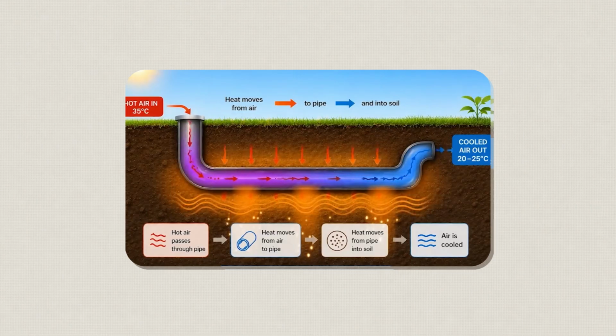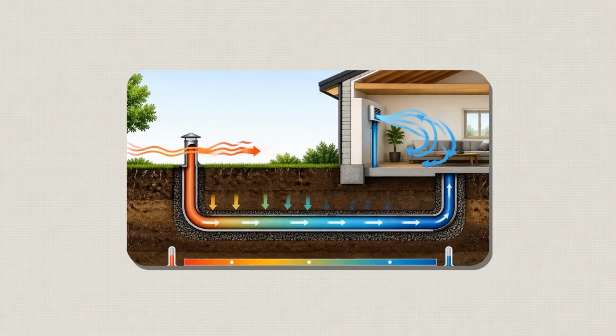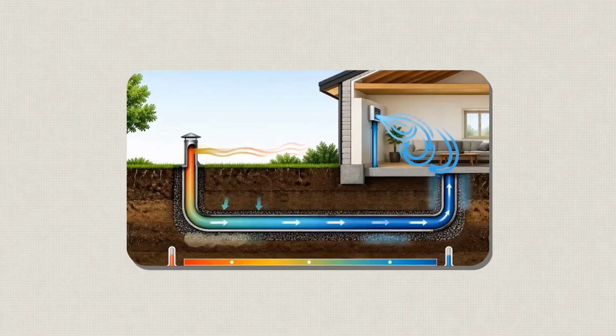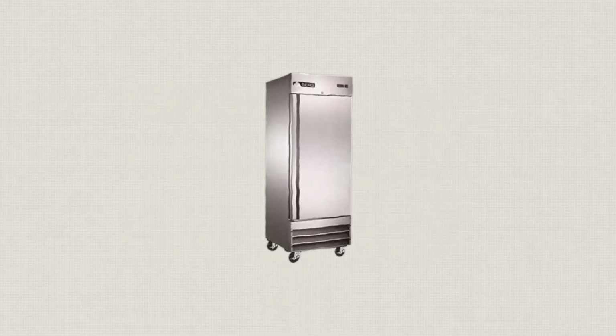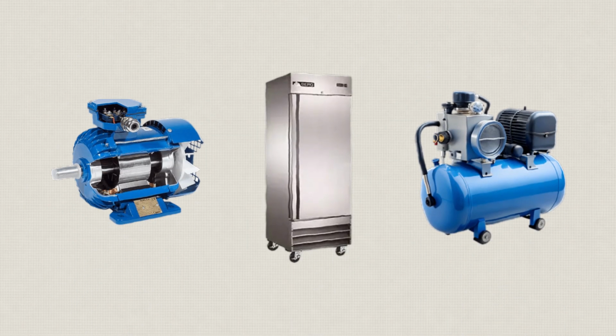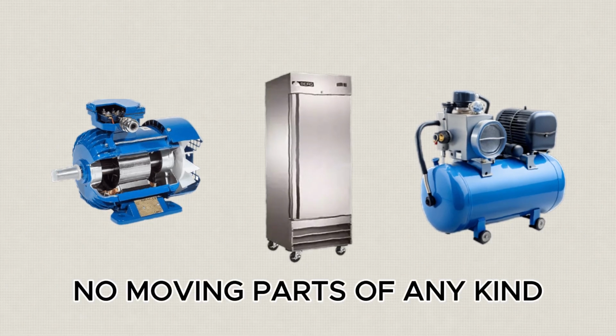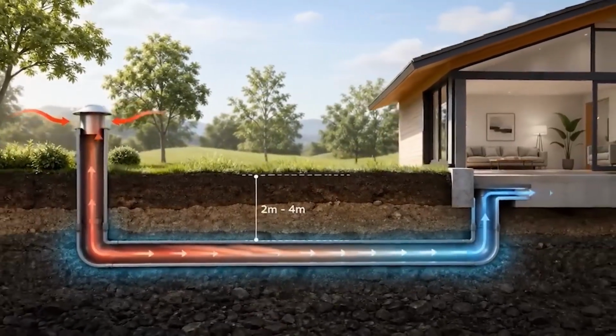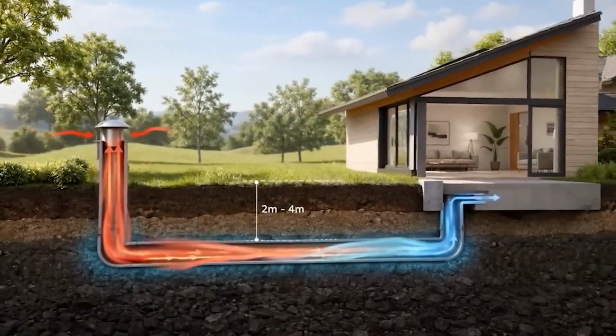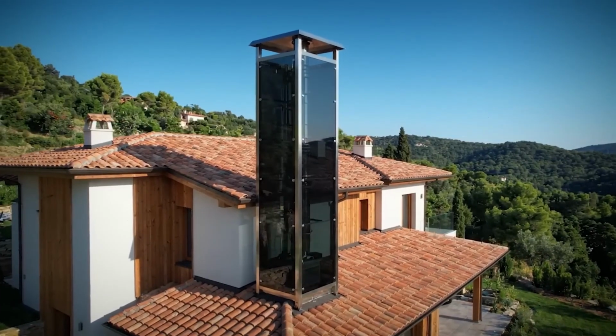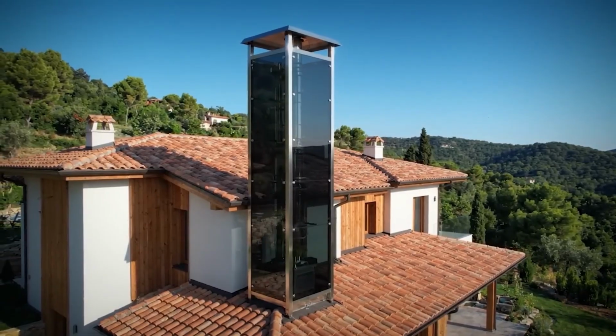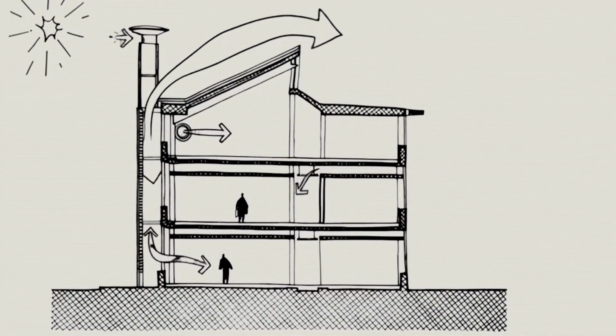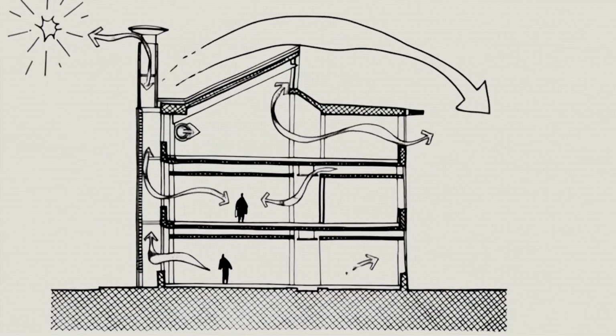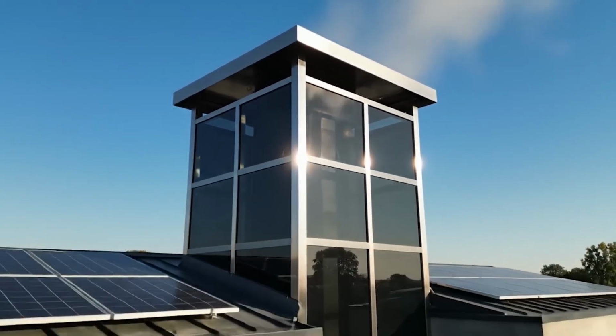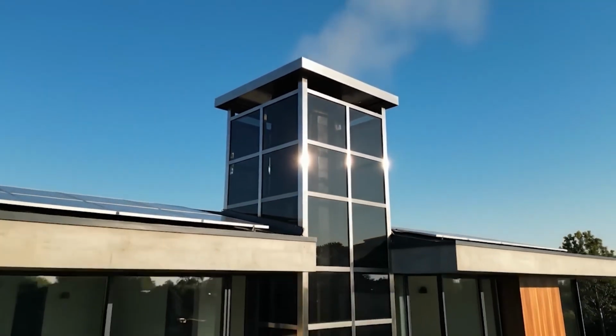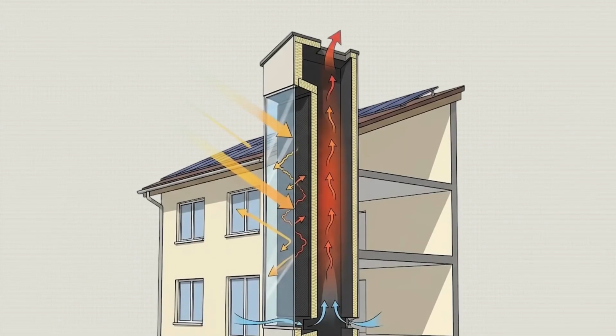By the time the air exits into the living space, it has been passively cooled by the temperature of the earth itself. There are no refrigerants, no compressors, no motors, no moving parts of any kind. The driving force that pulls air through the system can be entirely passive, powered by the stack effect of the building, a solar chimney mounted at the exhaust point, or a combination of both. When paired with a solar chimney, the system becomes a closed thermal loop. The chimney creates negative pressure at the top of the building. That suction pulls air through the earth tube at the base. The air enters pre-cooled.